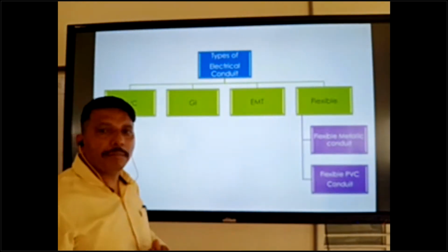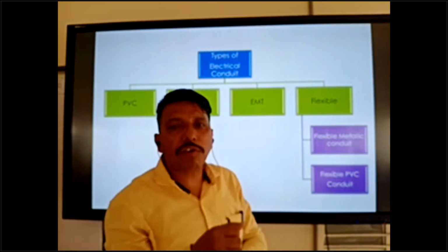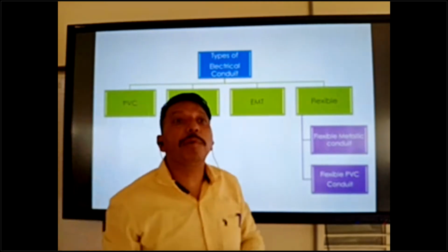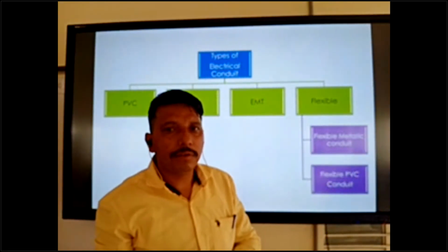We cannot use PVC in the open because if some material touches there, it gets damaged. So we cannot use PVC type in an open area. In the Gulf, we can use it inside the slab or inside the wall.